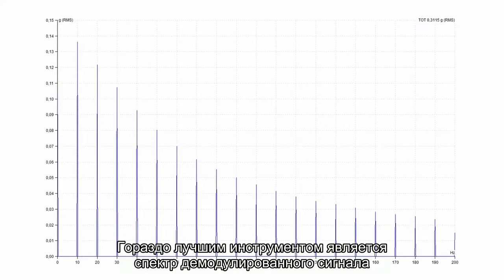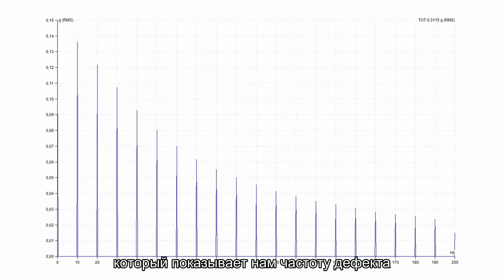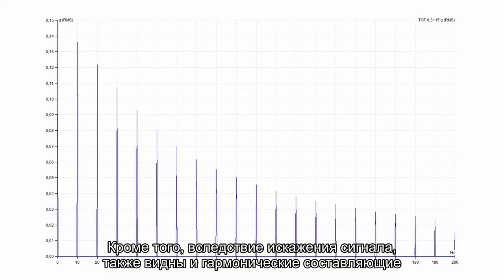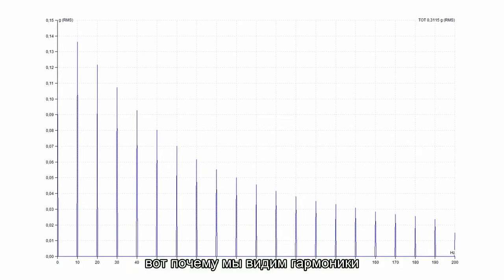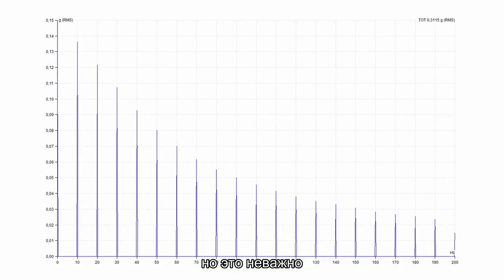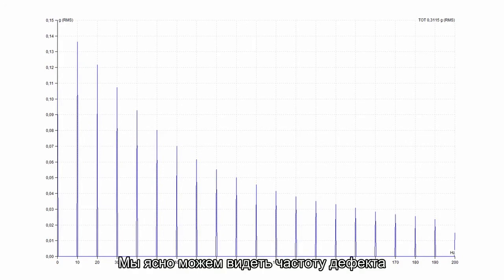A much better tool is the demodulation spectrum which shows the fault frequency to us. Additionally the harmonics are displayed because of signal distortion. It is not a pure sine wave. That is why we see harmonics. But it doesn't matter. We can see the fault frequency clearly.